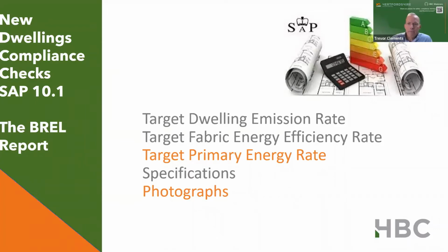That is about considering things like the insulation values for the thermal elements, the air leakage rates, thermal bridging issues, solar gain, heating system efficiency, all those sort of things that are used to calculate the energy demand for space heating and cooling. But we've got this third new highlighted metric, which is the target primary energy rate, and that's an all new factor, which I will explain a bit more in detail later.